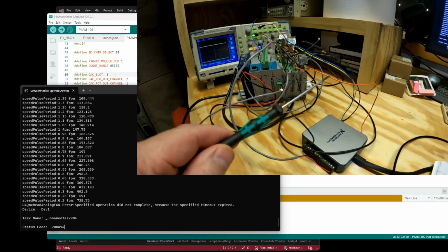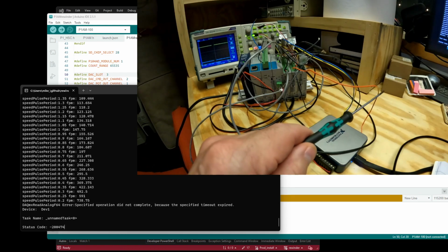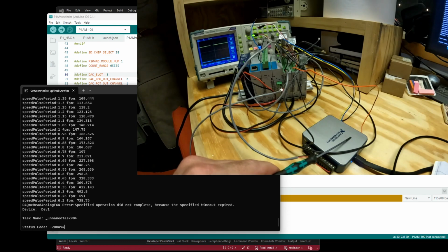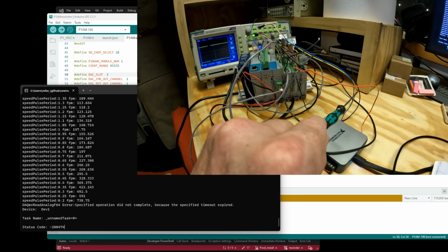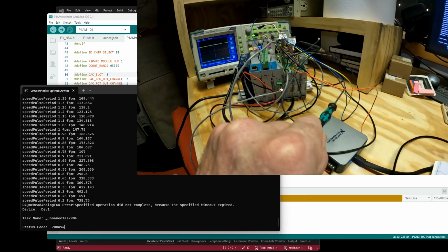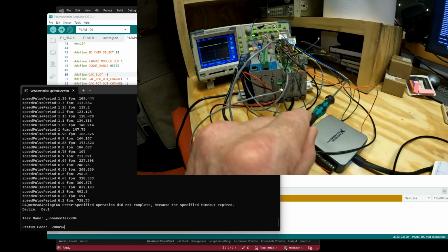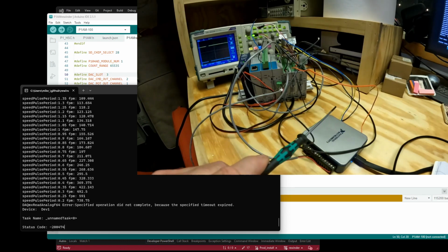The plant takes the command output, the orange wire, that's the servo valve amplifier voltage command, runs that through the plant model difference equations, maps the lateral motion that's modeled to LVDT output, also models the transport lag to the paper edge and outputs the edge sensor signal modeled.